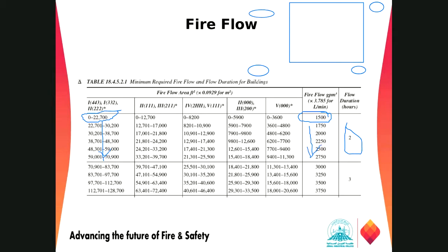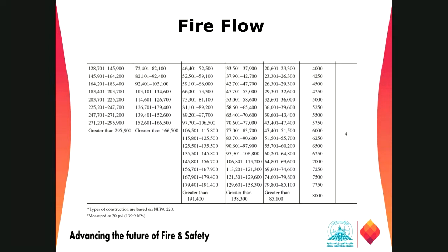And then if the area goes further, the capacity goes higher and the flow duration also goes to 3 hours. And in some cases, if you see this one, we need it for 4 hours. So it is totally based on the area of those interior premises and the type of construction. The construction type also affects the requirement, because highly combustible material will need a greater quantity of water.